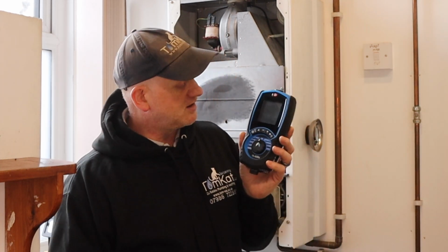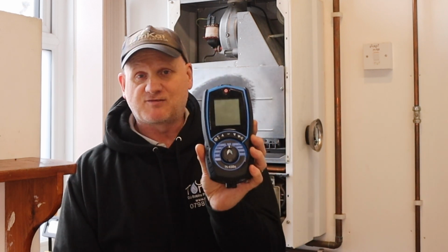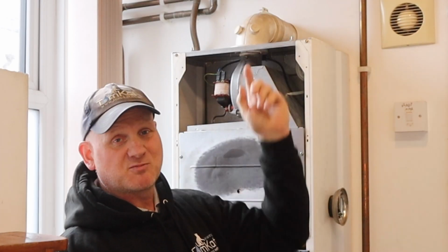Well, first of all, let's talk about annual servicing. Now, because everybody's going to be short of cash, I guess the first thing that's going to go is people having their boiler serviced. And also servicing, there's two different types of servicing. There's a full strip down service, or there's a service where a gas engineer will just rock up and use one of these little devices, which is a flue gas analyzer, and they'll stick it in the test point and analyze your boiler and walk away. That's not a service. That's a nothing.